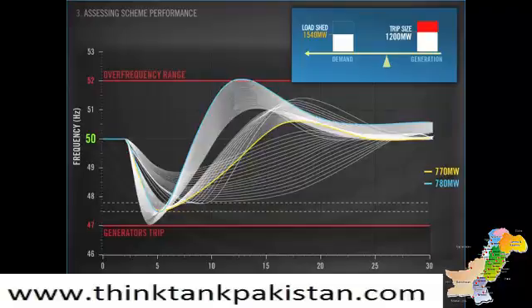This analysis gives us an overview of how the scheme performs over a range of results. It enables us to see when we are shedding too much and sending the frequency higher than 52 Hz. And it also gives us a picture of how the UFLS scheme performs for larger events, such as a 1200 megawatt loss. The drawback is that these traces are complex to read and interpret. This graph alone has around 90 frequency traces on it.